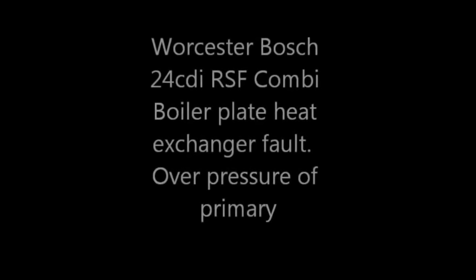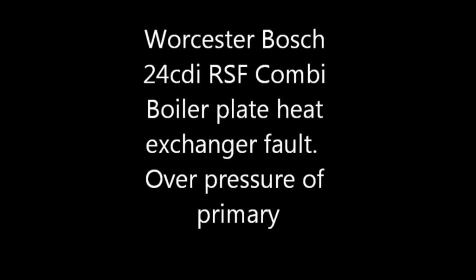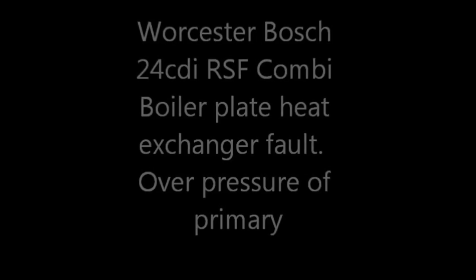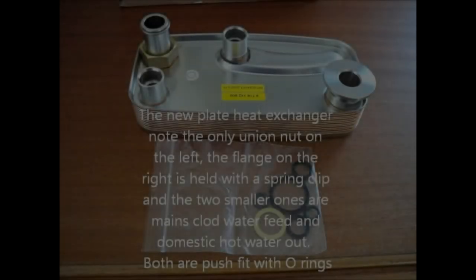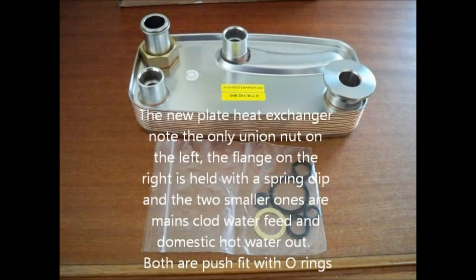Worcester Bosch 24 CDi RSF combi boiler plate heat exchanger fault, over pressure of primary. The new plate heat exchanger, note the only union nut on the left, the flange on the right is held with a spring clip, and the two smaller ones are mains cold water feed and domestic hot water out. Both are push fit with O-rings.